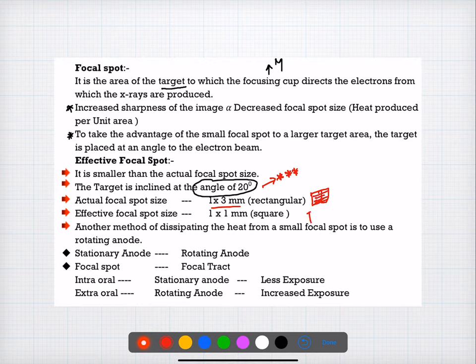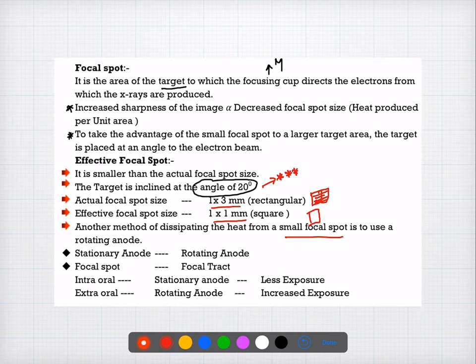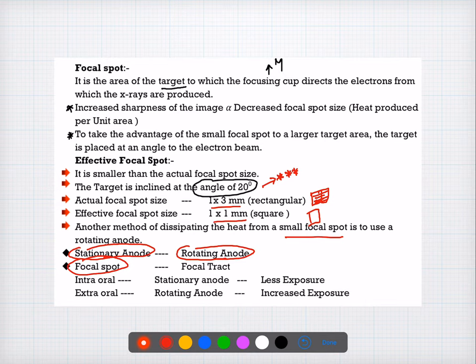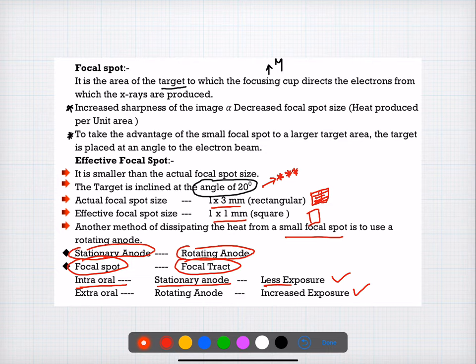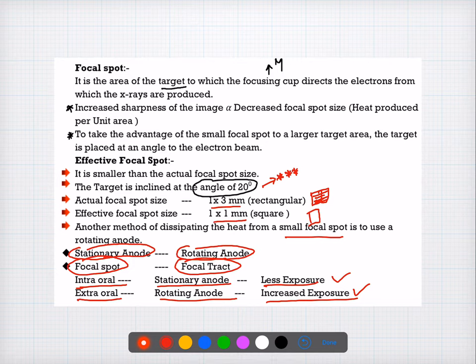The actual focal spot is 1×3 millimeters and is rectangular in shape, whereas the effective focal spot is square in shape at 1×1 mm. Other methods to dispense heat from the focal spot include the rotating anode. With a stationary anode the focal spot stays in one position; if the anode moves, the focal spot converts into a focal tract. In intraoral radiographs, a stationary anode with less exposure is used; in extraoral, a rotating anode with increased exposure is used.